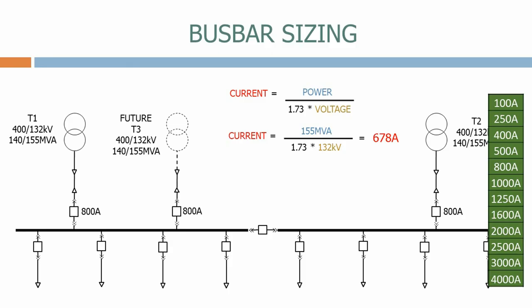Next, let's look at the busbar rating. It's important that when we're sizing the busbar, we include all future transformers in this calculation, as it's very difficult and expensive to change the busbars at a later date. So for this example, we have three transformers each carrying 678 amps. This gives a grand total of 2034 amps. Looking down the table, the correct busbar rating to choose is therefore 2500 amps. The busbar section breaker will carry the same current, so let's rate it at 2500 amps as well. We've now sized all of the equipment.